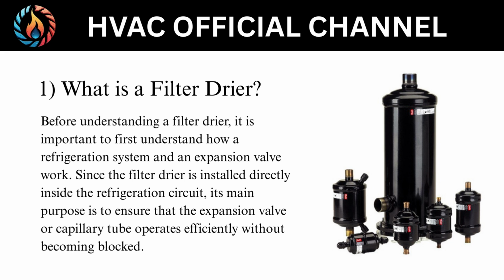1. What is a filter dryer? Before understanding a filter dryer, it is important to first understand how a refrigeration system and an expansion valve work. Since the filter dryer is installed directly inside the refrigeration circuit, its main purpose is to ensure that the expansion valve or capillary tube operates efficiently without becoming blocked.